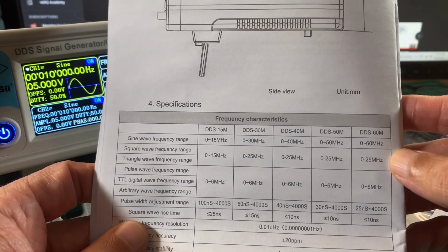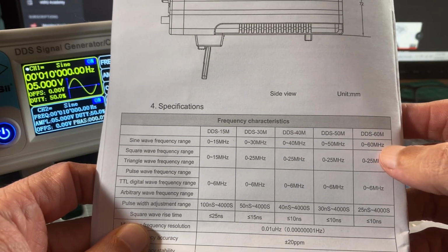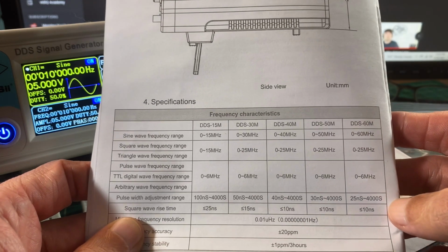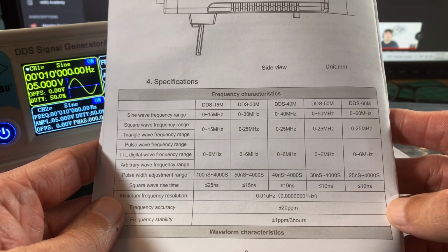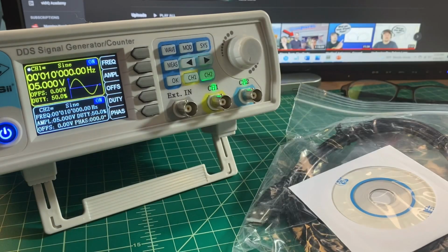I did want to point out in section 4 of the specifications, your frequency range is limited based off of the type of signal that you are using. So this is something that you may want to consider. This also shows the characteristics for multiple models. Here we have the 60.